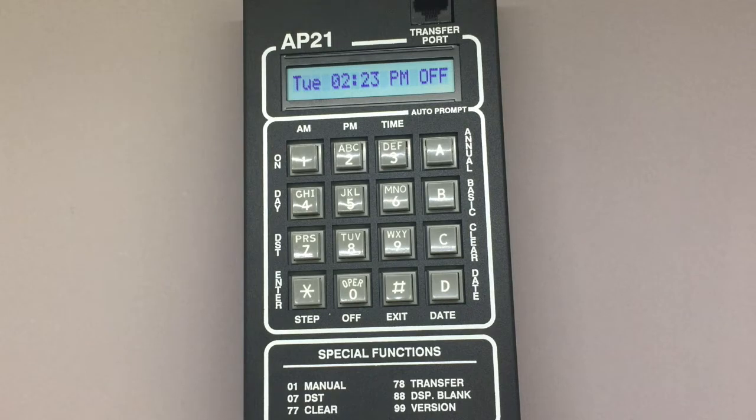On the AP21 you can program what RTC calls basic steps, which are scheduled times the AP21 stores in which the time switch automatically turns the flasher relay on or off. Each scheduled programming instance of on or off is referred to as a step.